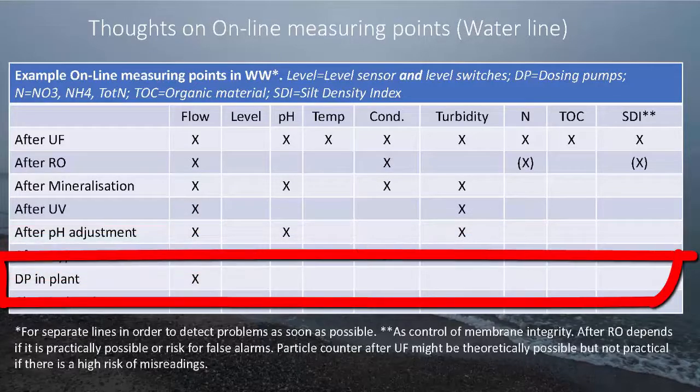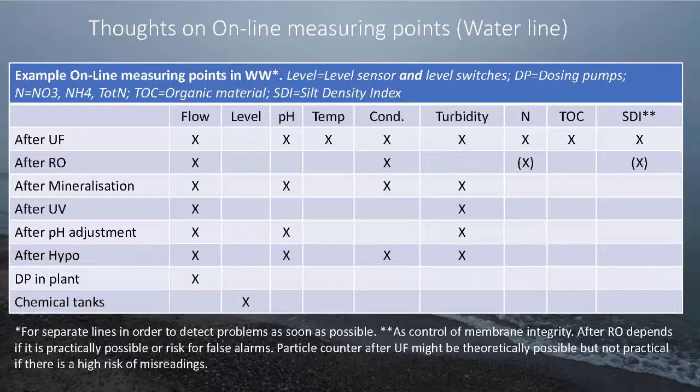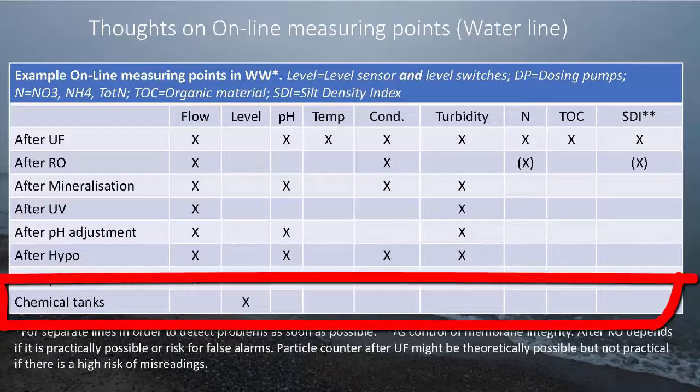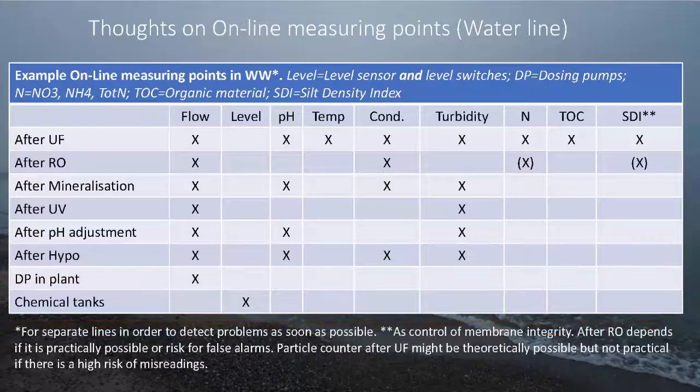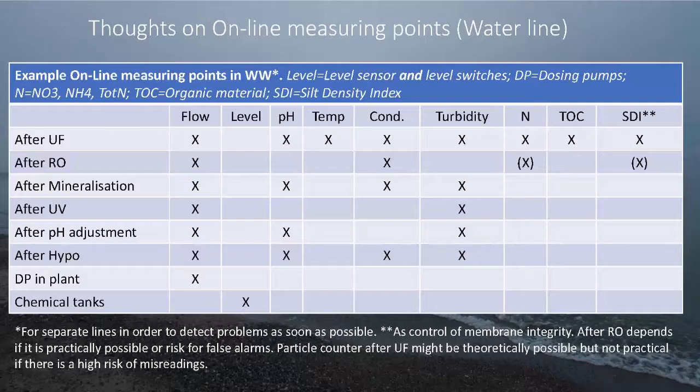And dosing pumps, the flow to the dosing pumps, every dosing pump so you see if something is wrong with the dosing. That is of course very critical. And in the chemical tank, you have level measurements so you are fully aware of the level and how much chemicals you have if you need to order or if you have an alarm level.